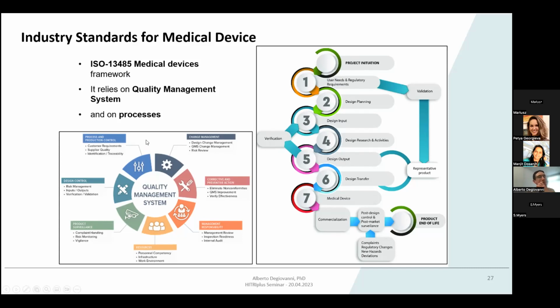And within this, the processes are defined, and the one that is very important to the transition from a research device to a product is really the design and development process, which basically starts from, as I said in the beginning, user needs and regulatory requirements that flow down into the design, and then into the design input for all the different subsystems, and in more detail for each single item. And each of them should go through a first loop, which is called verification, which basically checks that the design outputs are compatible with what was specified as a design input.